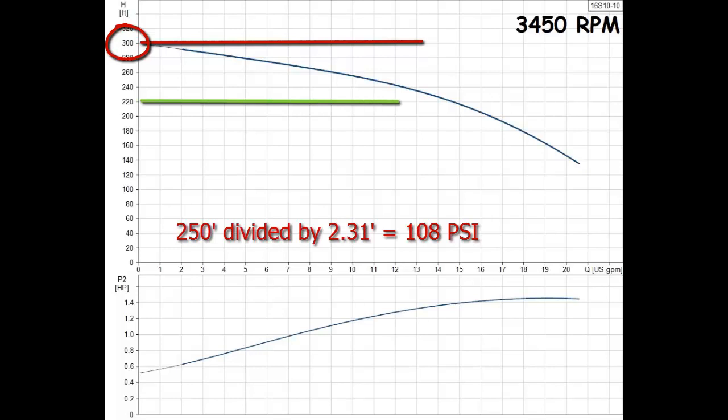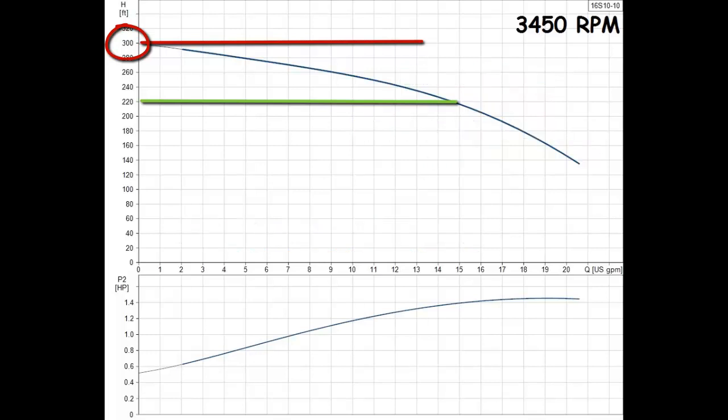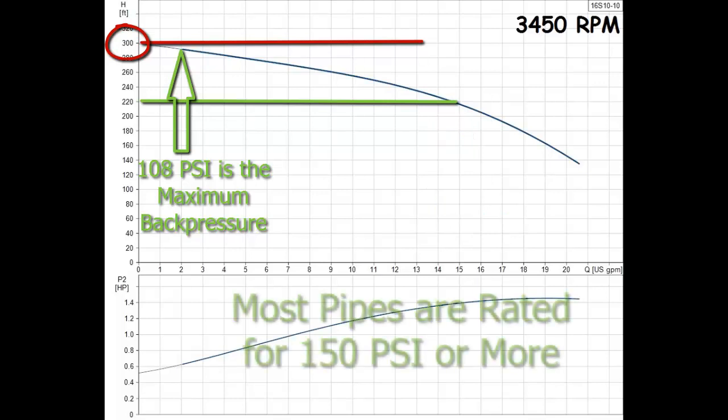So while the CSV is delivering a steady 50 PSI as flows vary from 15 to 2 gallons per minute to the house, the back pressure on the pipe before the CSV will vary from 50 to 108 PSI respectively. The back pressure must be lower than the pressure rating of the pipe and CSV, which is generally not a problem as most pipes are rated for more pressure than the pump can produce.